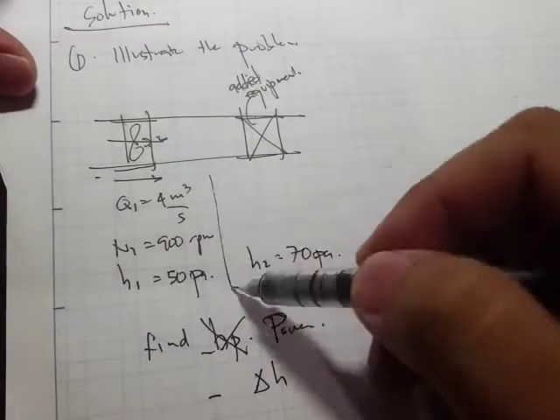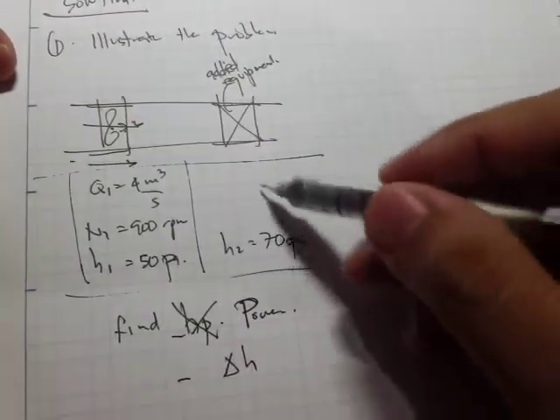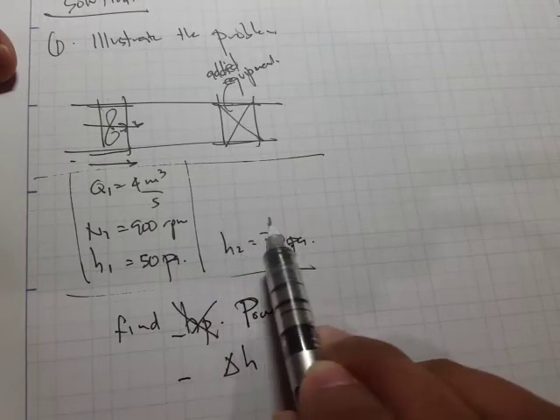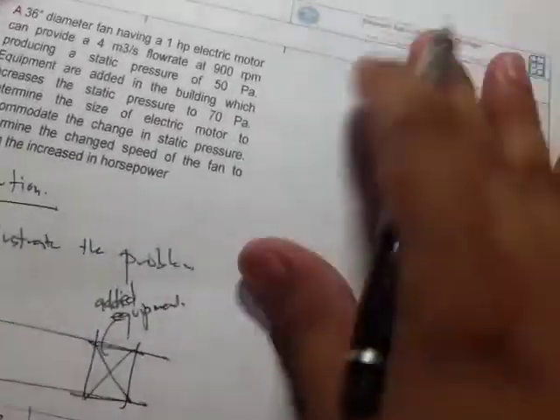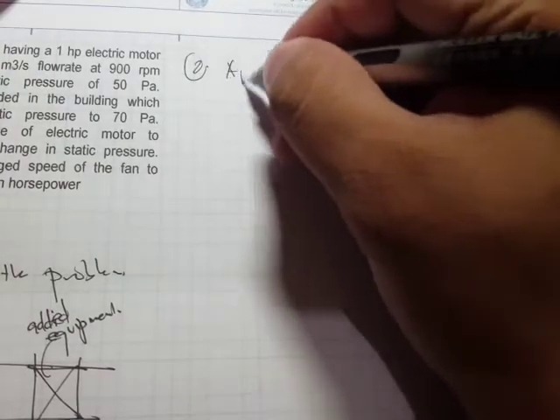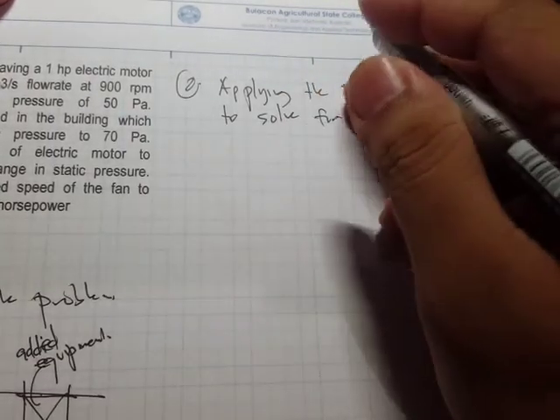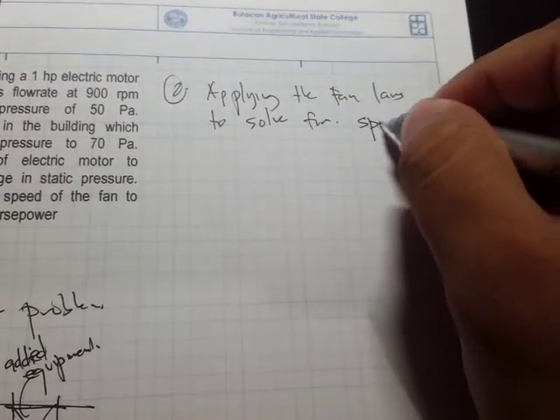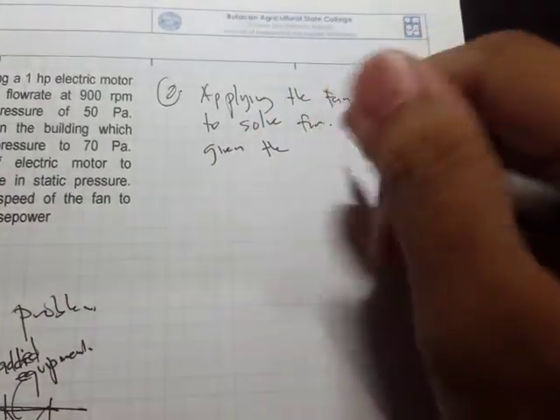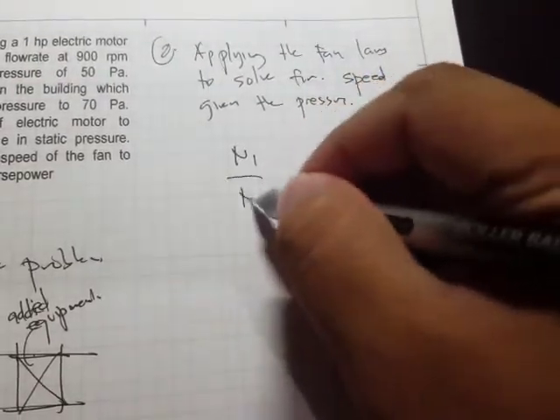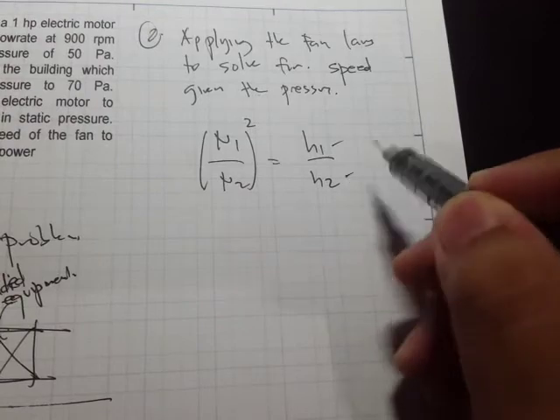Observing the problem, we have initial conditions and final conditions. We only have a value for head or pressure. Applying the fan laws to solve for speed given the pressure: recall n₁ over n₂ equals h₁ over h₂, and for static pressure this ratio is squared. So n₁ = 900 is given, h₁ = 50 and h₂ = 70 are given, so we can solve for n₂. Doing the calculation: 900 divided by n₂ equals the square root of (50 divided by 70).